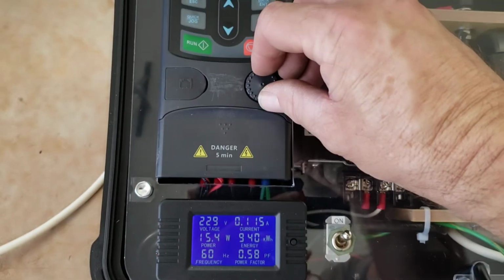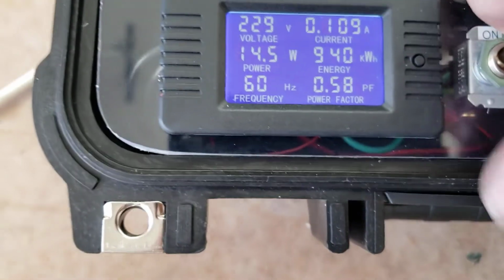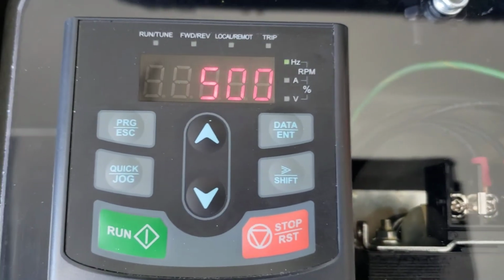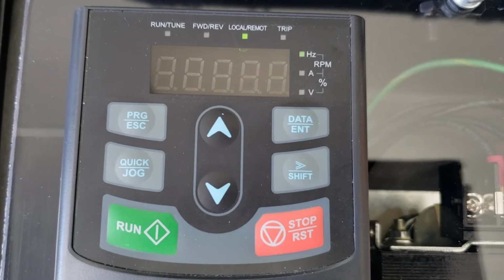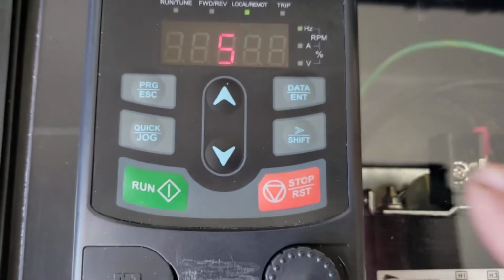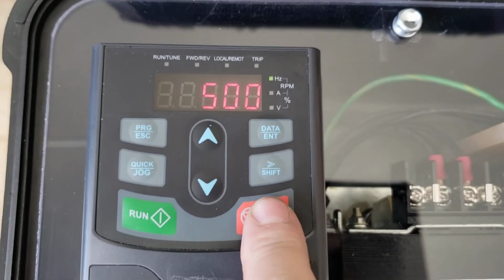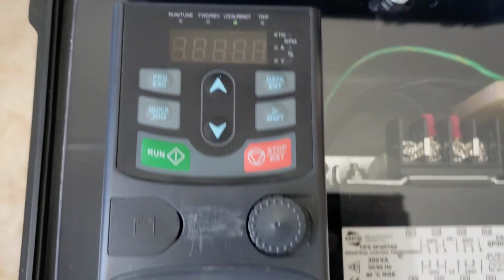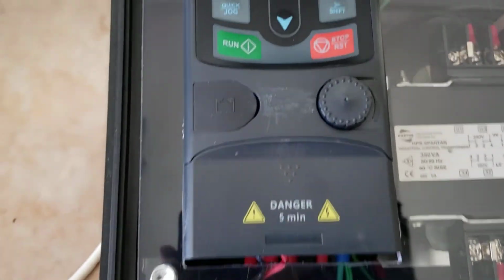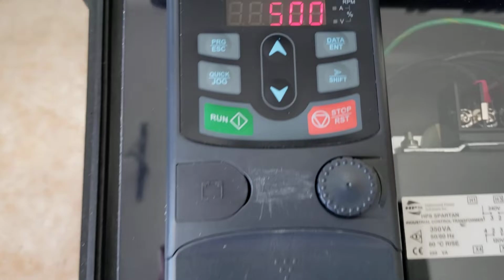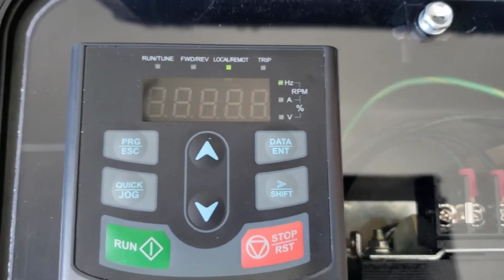So turn the potentiometer counterclockwise, turn it back down, turn it off. If you see an abnormal error like OC3 or something of that nature, you can reset it just by pressing this reset button. That'll clear that. You shouldn't see that. We've eliminated that. We're turning the sensitivity way down on that because it doesn't really function for what we're testing here.